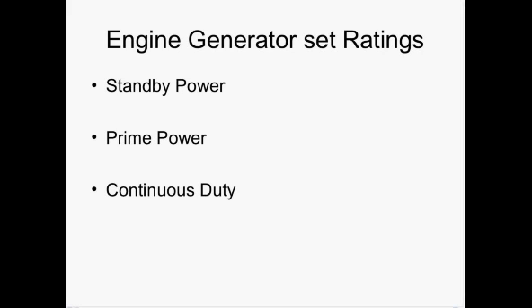Engine generator sets are rated according to the application they are used in. Most diesel engine-driven generator sets are rated for standby power. A prime power application is basically the same engine generator set, which is used for more than backup power. It can be run for more hours per year at a lower power level and still have an acceptable life expectancy. Generator sets used in utility programs to periodically reduce the load on the grid are rated for prime power.